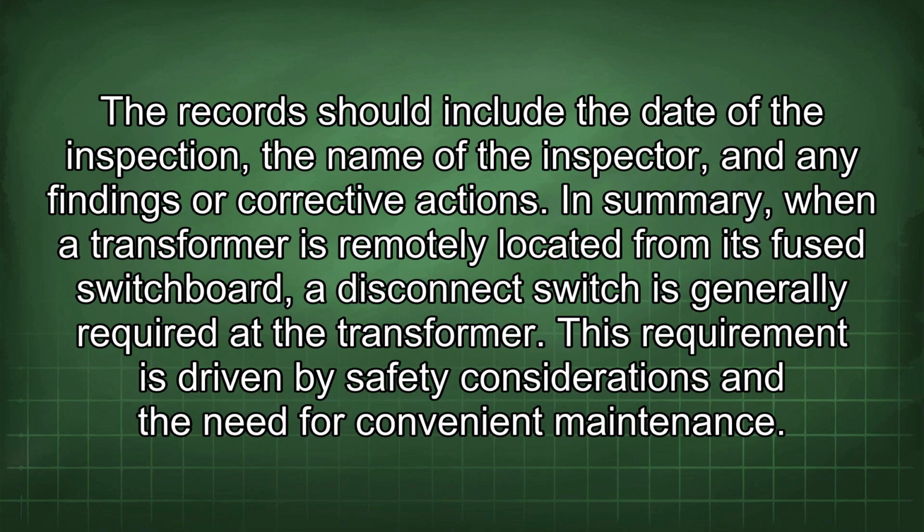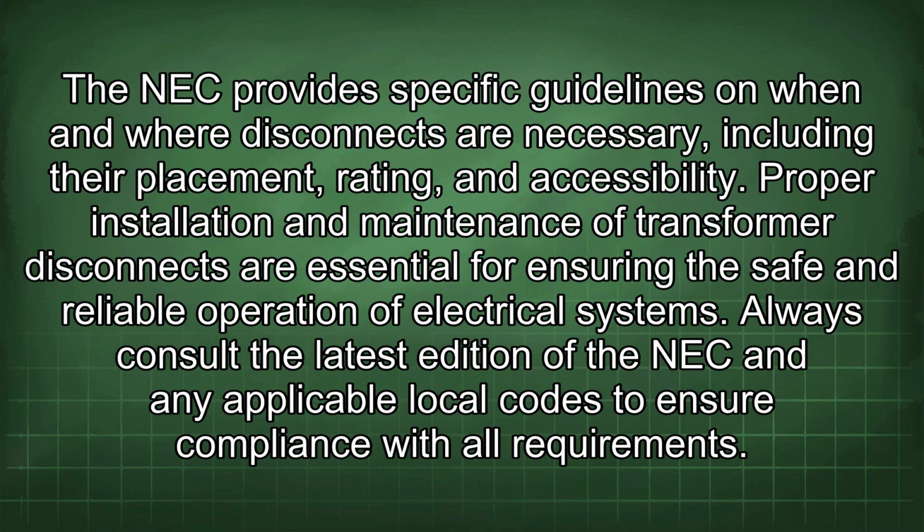In summary, when a transformer is remotely located from its fused switchboard, a disconnect switch is generally required at the transformer. This requirement is driven by safety considerations and the need for convenient maintenance. The NEC provides specific guidelines on when and where disconnects are necessary, including their placement, rating, and accessibility. Proper installation and maintenance of transformer disconnects are essential for ensuring the safe and reliable operation of electrical systems.